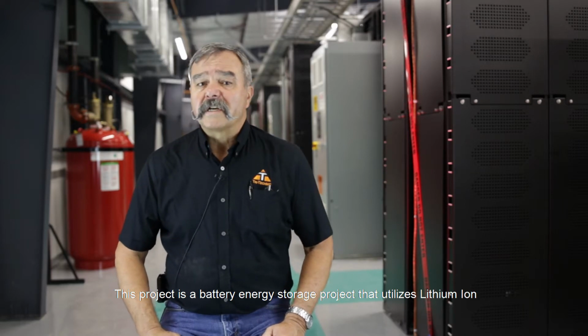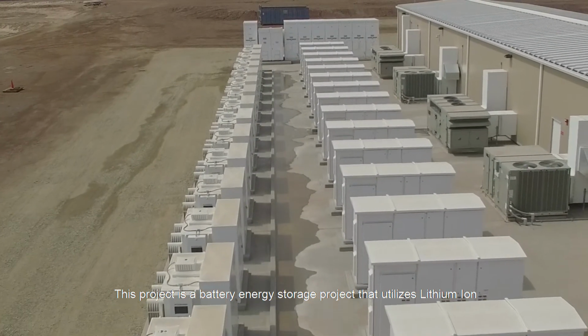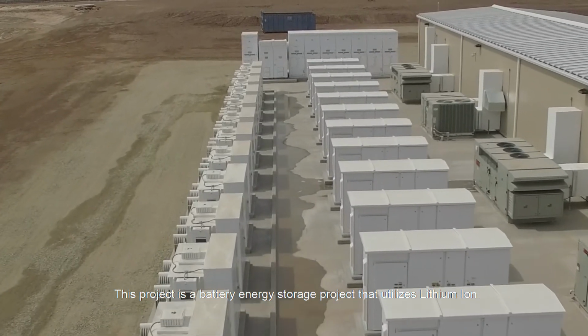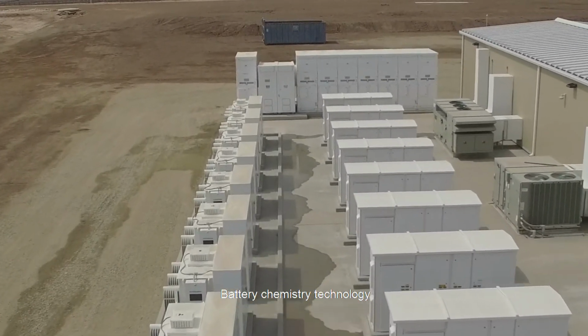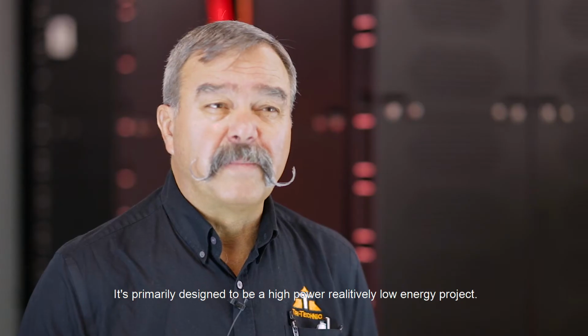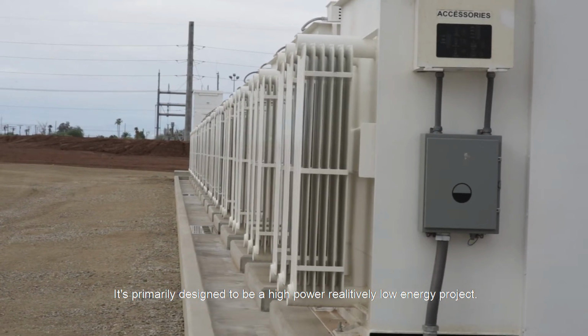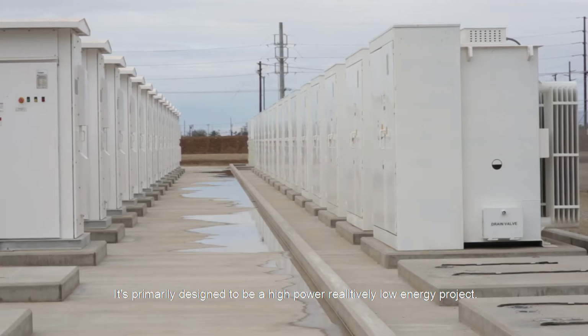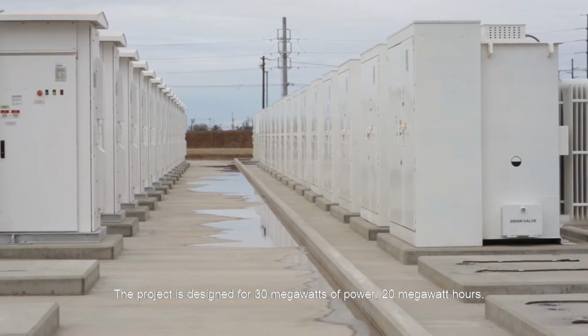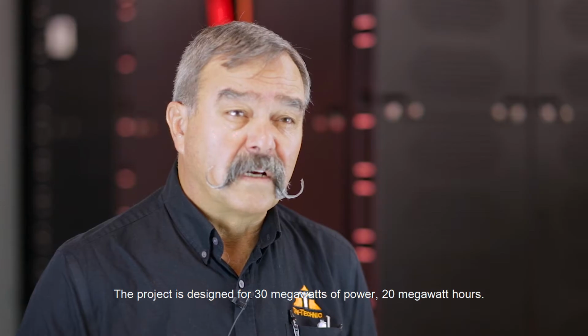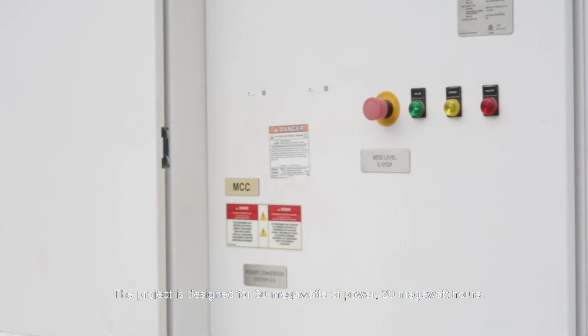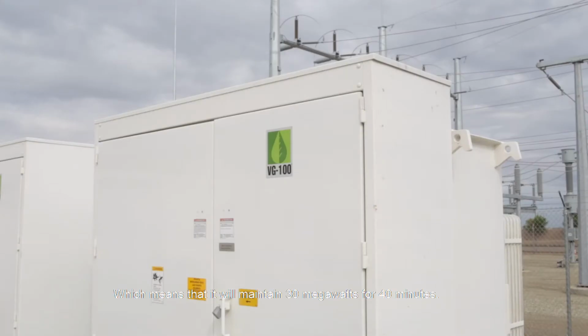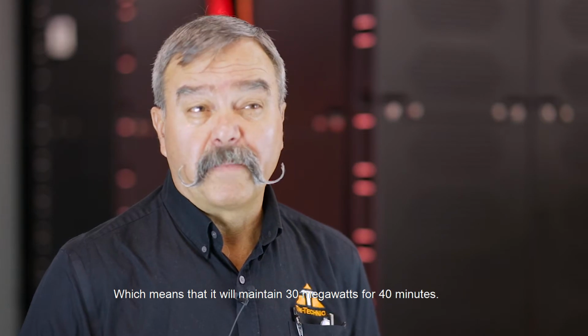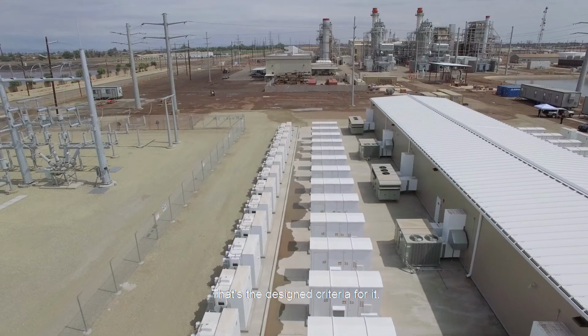This project is a battery energy storage project that utilizes lithium-ion battery chemistry technology. It's primarily designed to be a high-power, relatively low-energy project, designed for 30 megawatts of power, 20 megawatt hours, meaning it will maintain 30 megawatts for 40 minutes. That's the design criteria for it.